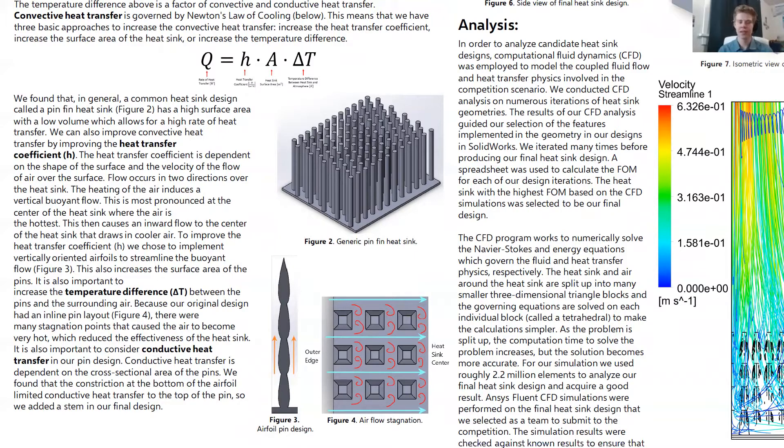Because our original design had an inline pin layout, as shown in figure 4, there were many stagnation points that caused the air to become very hot, which reduced the performance of our heatsink. Our final design used a staggered pin layout with cylindrical cross-sections to improve this.